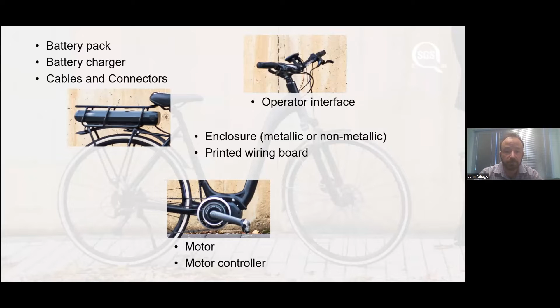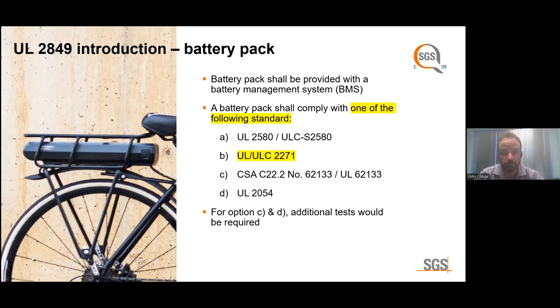So we'll start with the battery pack. The battery pack shall have a battery management system, which we call a BMS. That's really what controls and protects the charging and discharging of the battery. Now, UL 2849 is quite flexible. You'll see as we go through this presentation that it has some flexibility on what standards to use for component approval, but it does require review and approval of the components. For the battery pack, you have 4 options. Options C and D are generally not vehicle specific, so if your battery is certified to those standards, there's some additional testing that's going to be required in UL 2849. The preferred standard for the battery pack is to be certified to UL 2271. And as New York City actually requires that, that's pretty much the option now: to go after 2271.